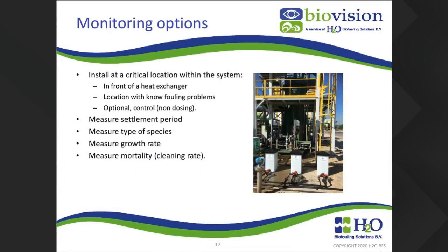The question is where do you put the monitor in a system? That's more or less always the question. Generally, we advise to put a monitor in front of the furthest heat exchanger or condenser to have the longest residence time within a cooling water system. But also you can install the monitor at a location where there is a known and historic fouling problem to get insight at that specific location. Optionally, you can install a second monitor as a control, at a spot where there is no chemical dosing, to have a comparison on efficiency.